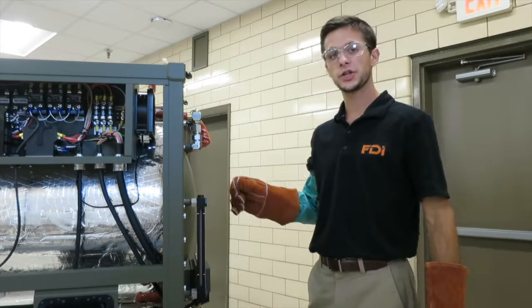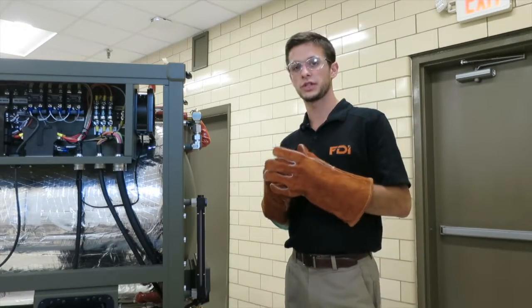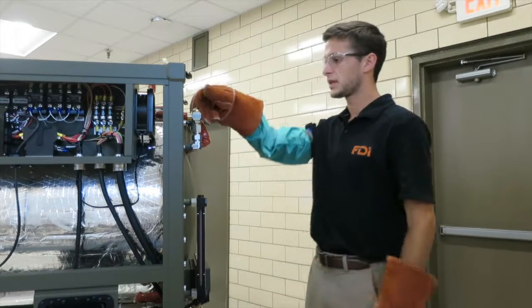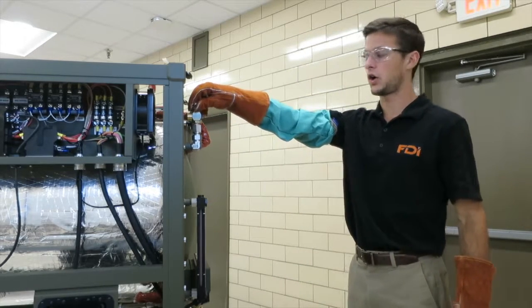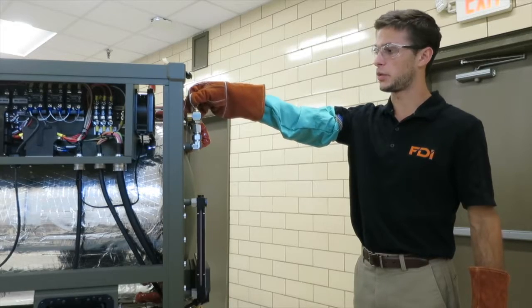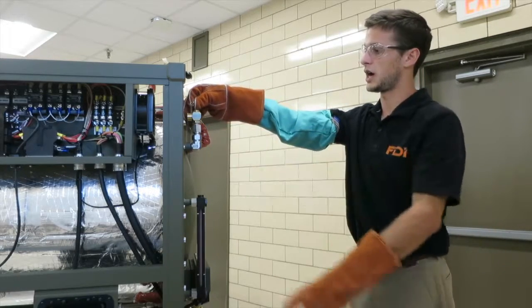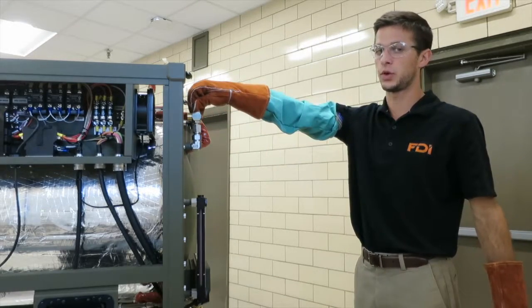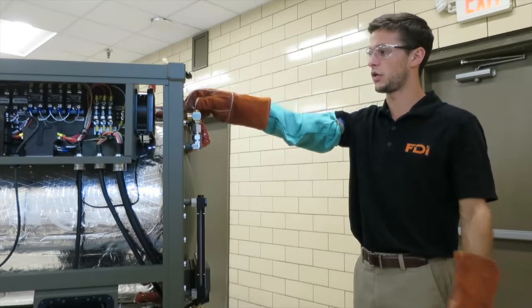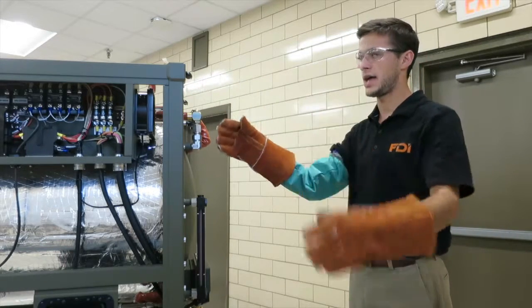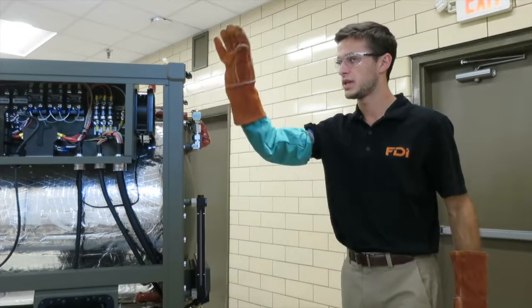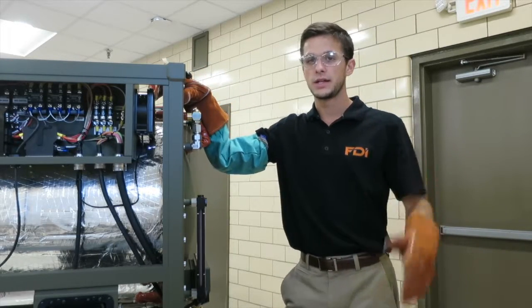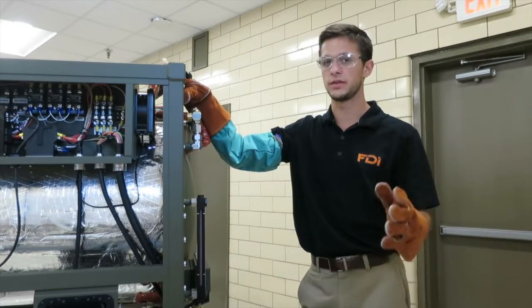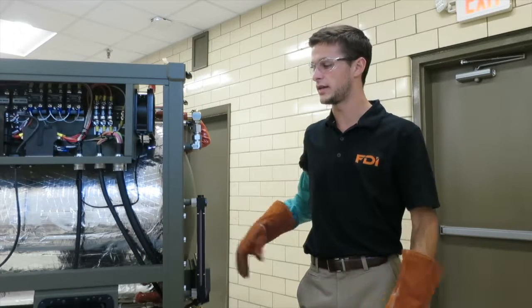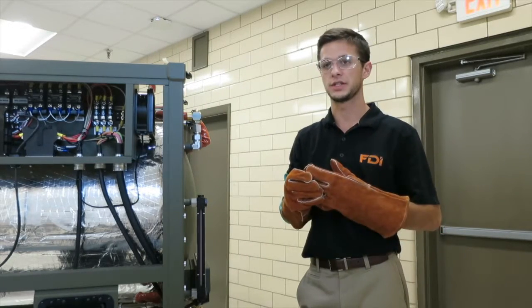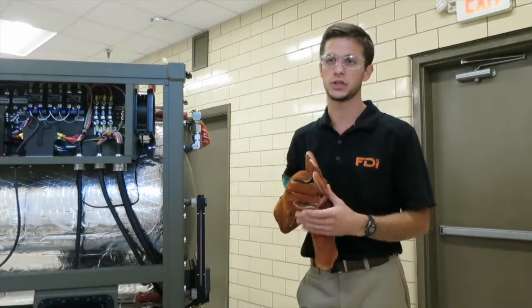So again, this is depressured, but we're just going to show you what to do every 2 months. Just stand arm's length away, and you're just going to pull this ring right here on top up for 2 seconds and hold, and make sure that the steam exits the pressure safety valve. So that's the only test for every 2 months, but again, remember to fully drain if you're not going to use it, as a good preventative maintenance from biological growth.